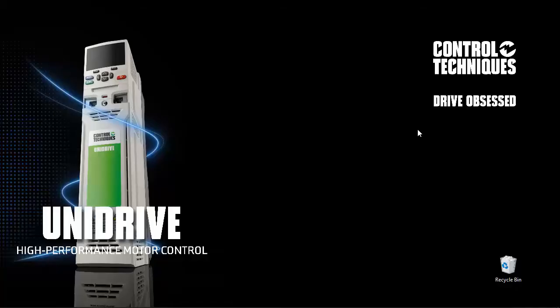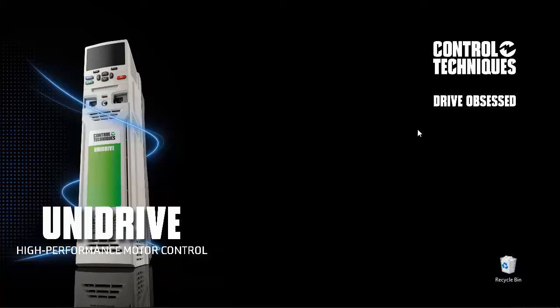I'm going to demonstrate how to use the device discovery tool in Machine Control Studio to set the IP address for the Bus Coupler. But before I do that, it's important that you understand how the device discovery service works in the first place. What I mean by that is whenever you want to use the device discovery service to set an IP address, you should always set a static IP address on your computer to your desired sub-network first. Let me show you.